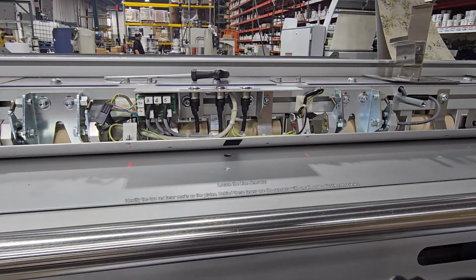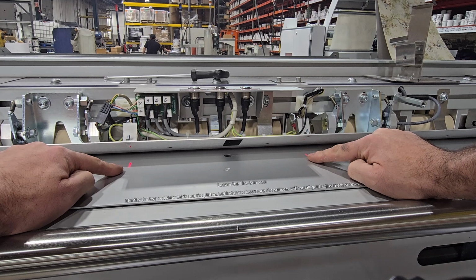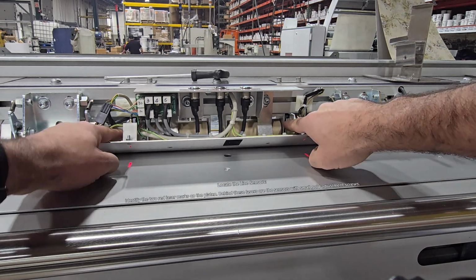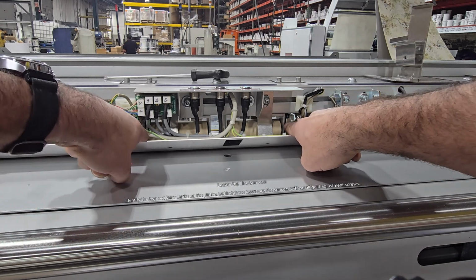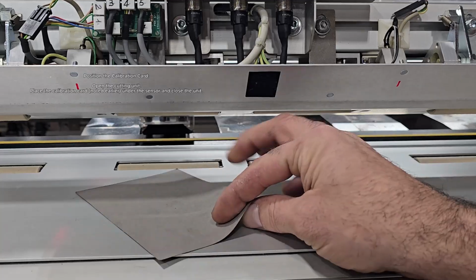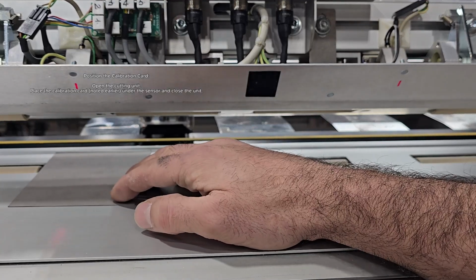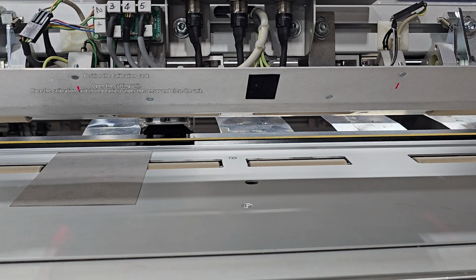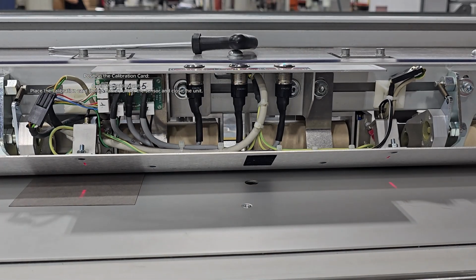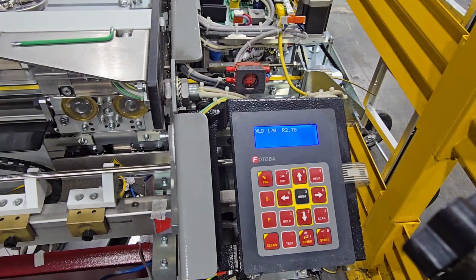Locate the line sensors. Identify the 2 red laser marks on the platen. Behind these lasers are the sensors with small gold adjustment screws. Position the calibration card. Open the cutting unit. Place the calibration card noted earlier under the sensor and close the unit.